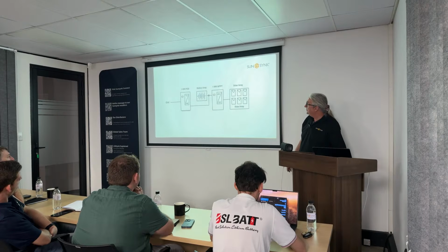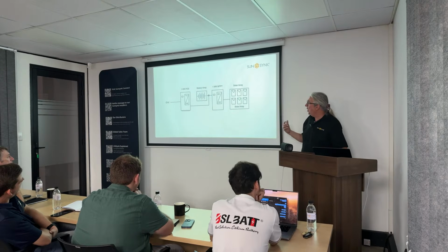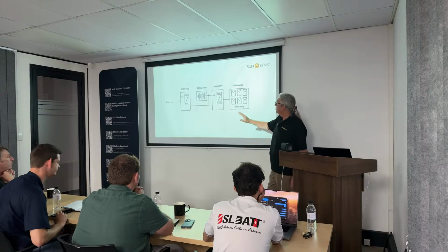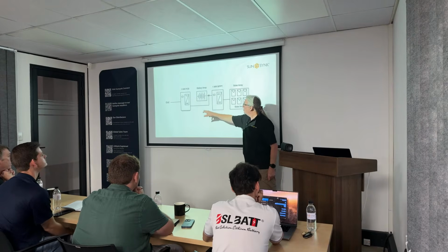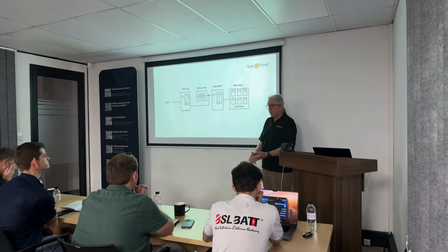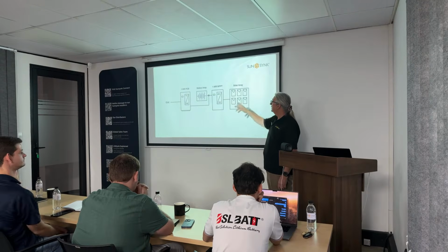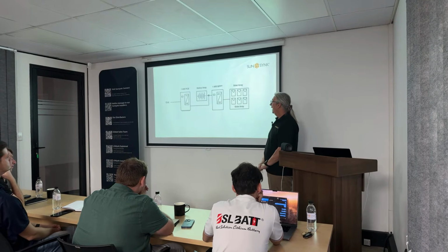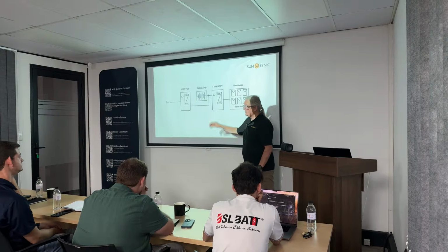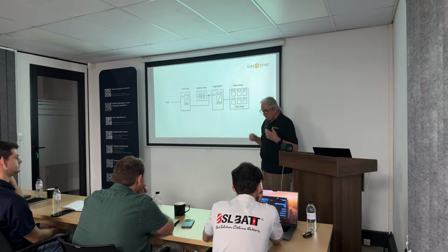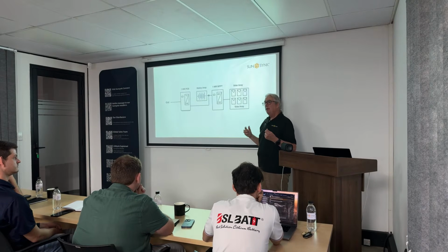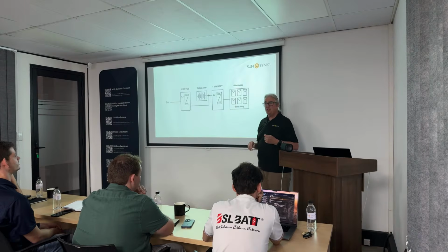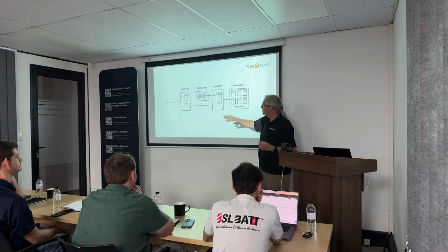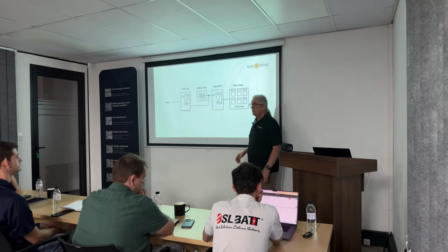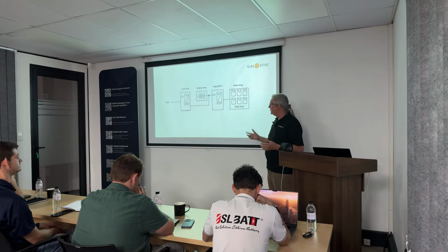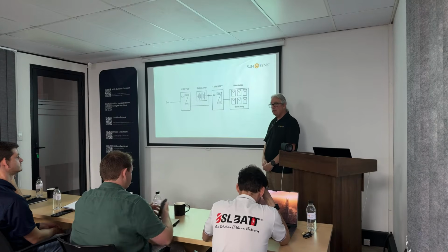As I go forward, there are different options. This is where we're using a larger unit, just an MPPT module and just a PCS cabinet. So it's a single cabinet with just PCS and a single cabinet with just MPPT. The PCS has the AC equipment on it, your breakers and everything else. The MPPT is just DC coupled, and on this one we'll also have a DC breaker. So they're all coupled by DC cables. You'll see there are big heavy DC breakers in the cabinets themselves.